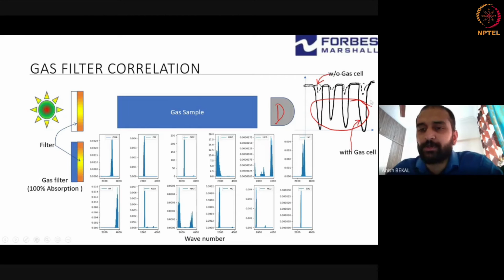When you take the ratio, interferences get cancelled out, whereas the gas itself has a fingerprint, and that ratio is what the detector picks up. By doing this, you can cancel interference quite a bit, though it's still not perfect absorption. One of our analyzers uses this technique, and it's quite robust for measuring concentrations in the 0 to 500 or 0 to 1000 ppm range.